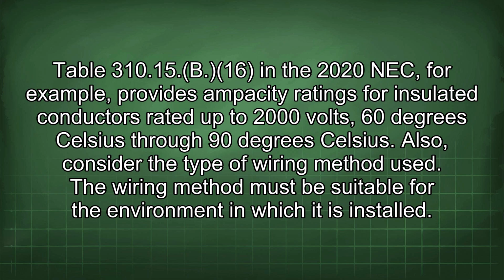Table 310.15(B)(16) in the 2020 NEC, for example, provides ampacity ratings for insulated conductors rated up to 2000 volts, 60 degrees Celsius through 90 degrees Celsius. Also, consider the type of wiring method used. The wiring method must be suitable for the environment in which it is installed.